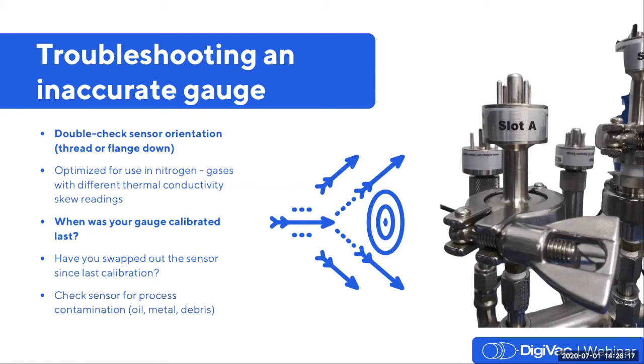Next to consider is, when was your gauge calibrated last? Even a rarely used gauge used in clean, dry air won't stay perfectly calibrated forever. And since there's no such thing as a perfect vacuum here on Earth, contaminants will infiltrate any vacuum system. When foreign matter meets the sensor, it alters the wires within, creates a coating over them more specifically, and those readings will drift and become less accurate over time. This is a totally normal side effect of use and not a sign of damage.